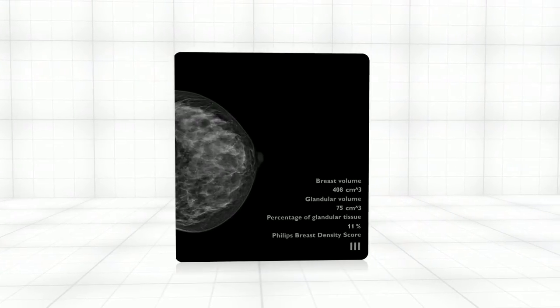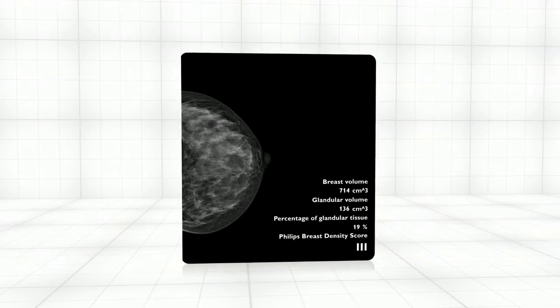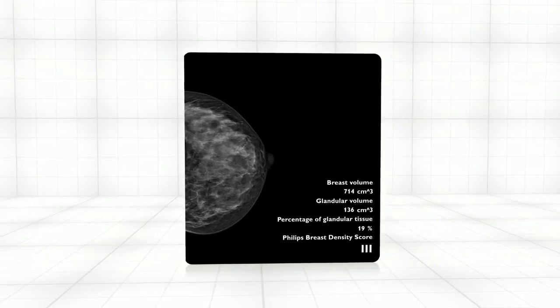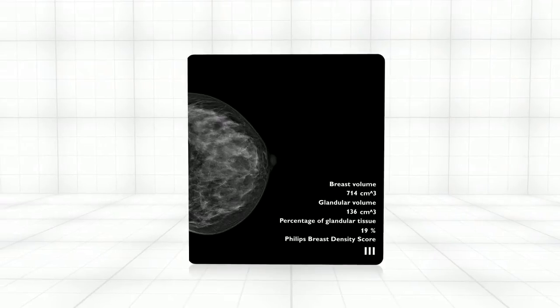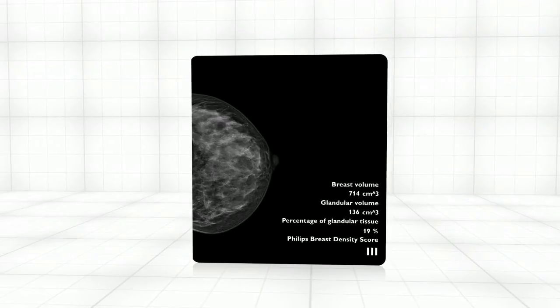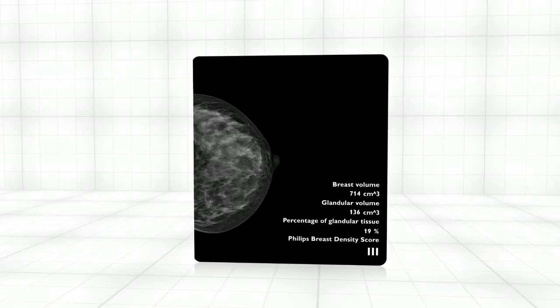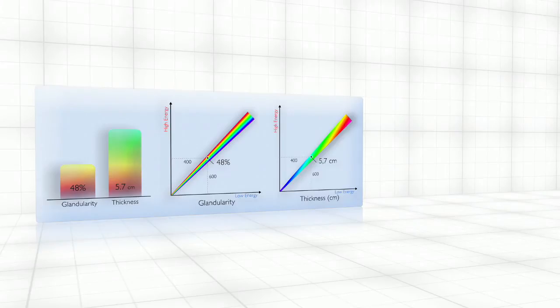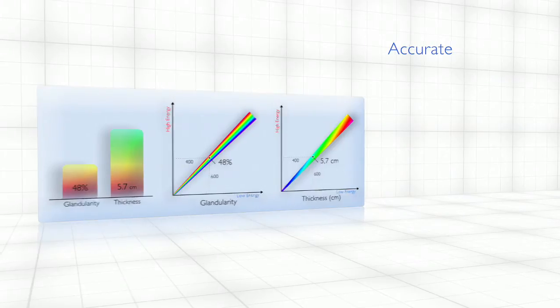Once that is calculated, MicroDose SI assigns the image with a density score that correlates to BI-RADS breast composition score. The breast density data is stored in the DICOM header, is available as a DICOM structured report, and is displayed in the image. MicroDose SI can provide a measurement of the volume of glandular tissue in the breast with high accuracy. In fact, phantom studies of spectral breast density measurement indicate that it can measure breast density with an error of less than 2%.